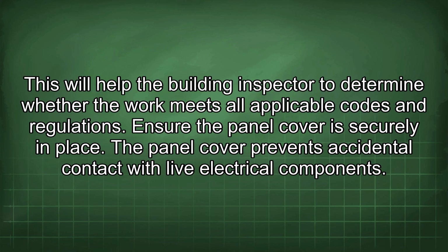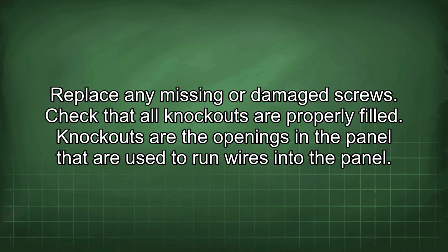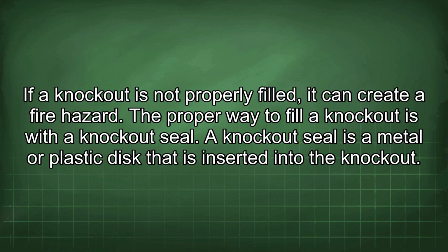Ensure the panel cover is securely in place. The panel cover prevents accidental contact with live electrical components. Replace any missing or damaged screws. Check that all knockouts are properly filled. Knockouts are the openings in the panel that are used to run wires into the panel. If a knockout is not properly filled, it can create a fire hazard. The proper way to fill a knockout is with a knockout seal. A knockout seal is a metal or plastic disc that is inserted into the knockout.